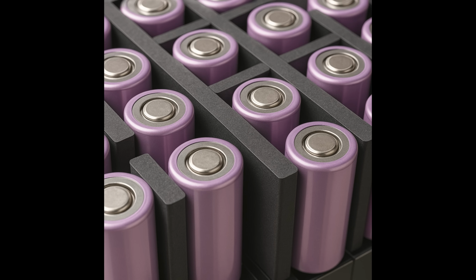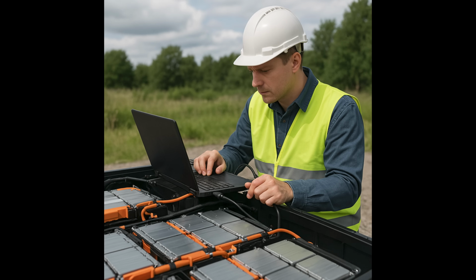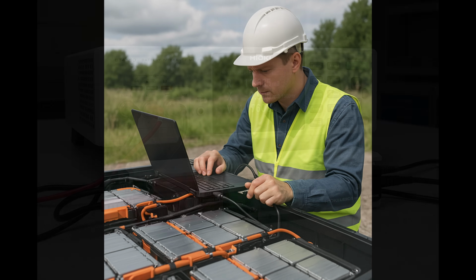And design modules to isolate and contain any single cell thermal event. In the field, it's critical to have regular inspections and maintenance, perform periodic checks of battery condition, capacity, internal resistance, and overall cell health, and remove or replace cells or modules showing early signs of degradation.